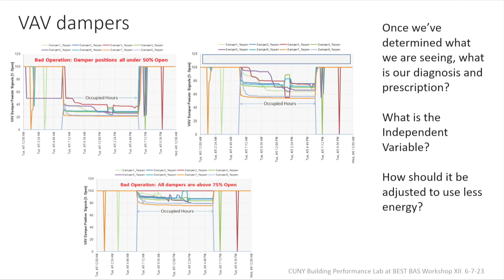This is what we would expect to see normally, where the dampers are controlling in a reasonable temperature range, and they're varying. The damper positions are all varying based on what's happening in the actual room. Some may be core, some may be perimeter, some may be south, some may be east, some may be occupied, some may be not occupied. And they're all in this 60 to 80% open range. And that's kind of the normal condition where our static pressure is doing what we would think. And again, this is a constant static pressure.